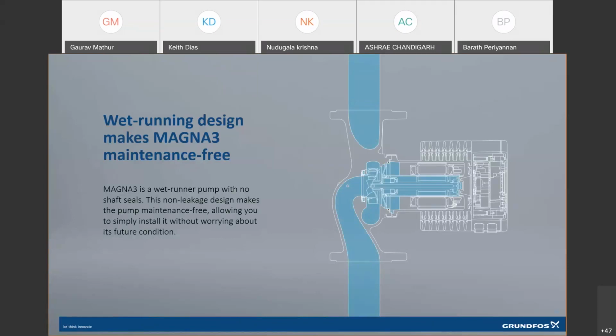One more feature which makes the system much more reliable: just a few days back we had a panel discussion, and one of the points discussed was, why do we really need standby pumps? If the pumps are reliable enough to ensure a trouble-free life, then why do we really need standby pumps? And that is an answer from Grundfos to this requirement of the market: we have the Magna 3 pump, which is a mechanical seal-less pump. If you see data from any pump manufacturer, the maximum failure in a pump happens at the area of the mechanical seal. And this pump is a sealless pump and ensures that reliability and maintenance-free operation are achieved with the help of Magna 3.